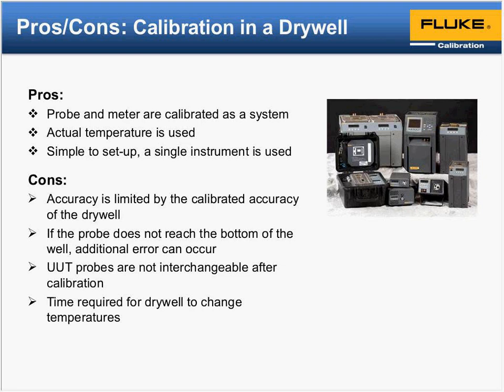So the big thing to take away when you're looking at the probe and the readout versus system calibration is that with the system calibration, any error that's contributed by the probe will be compensated through the readout piece. So that's one thing there.